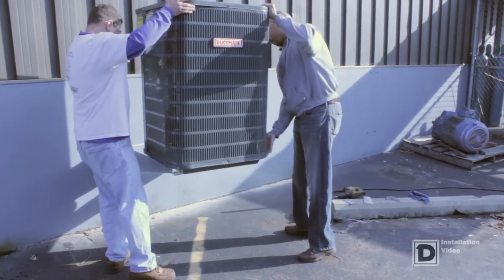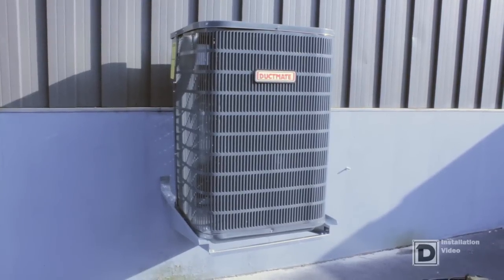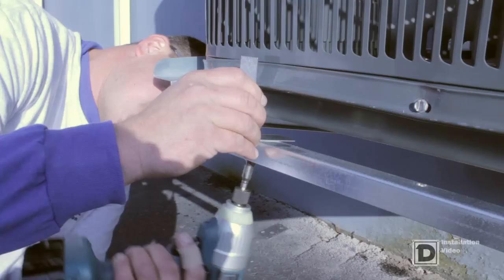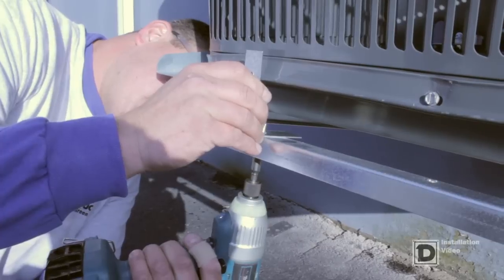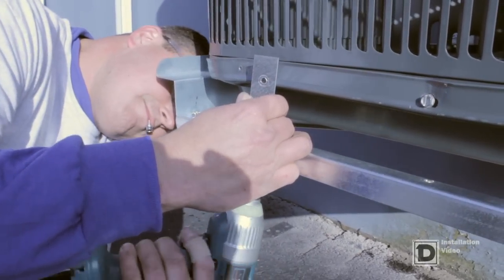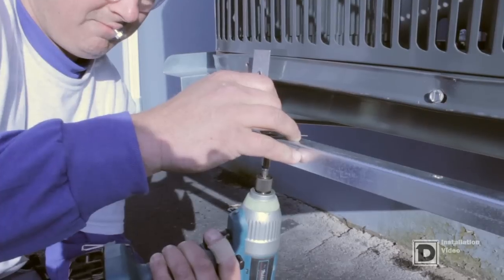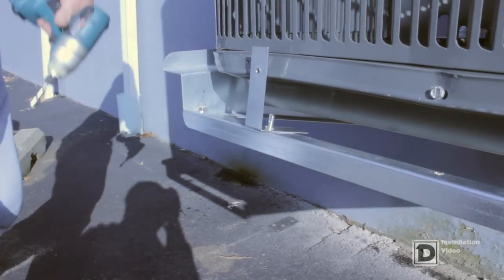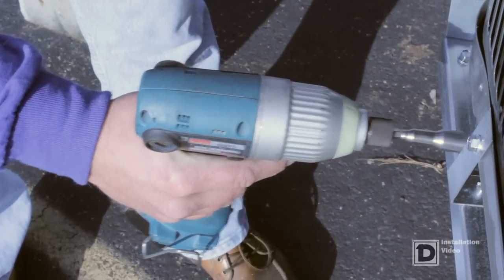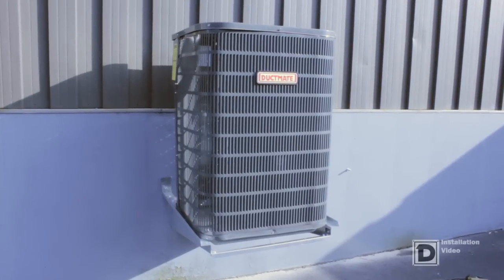Position the AC condenser on the stand. In areas requiring hurricane restraints, strapping is needed for inland and coastal areas. Attach the bottom side of the AC unit to one 1-inch by 22-gauge galvanized hurricane strap to the front cross support with a 3-quarter, number 14 galvanized, self-tapping screw. Hurricane straps should have no slack. Maximum spacing is 12 inches on center.